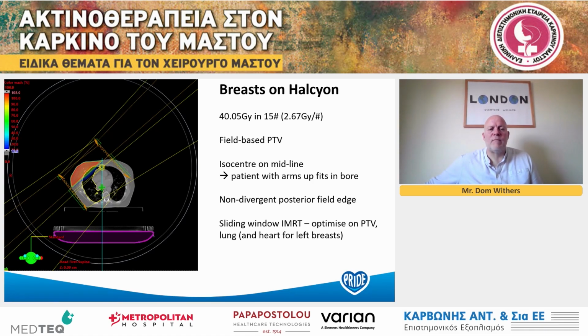If your scan does not include the whole of your patient, you need to be very confident that they are not going to hit the bore. We know that our patients go through our 80 centimeter CT scanner with no lateral movement. Of course, there's no lateral movement on the CT couch. So if we treat on midline and we know that the couch will fit down here on the Halcyon, then we know that if we move them into the Halcyon bore, there will be lots of room inside and they will not hit the bore as well. Before we started treating breasts on Halcyon, we had some very kind volunteers who were existing breast patients on one of our clinics, and they very kindly offered to, after their treatment on certain days, come to the Halcyon to be set up as if they were being treated on the Halcyon.